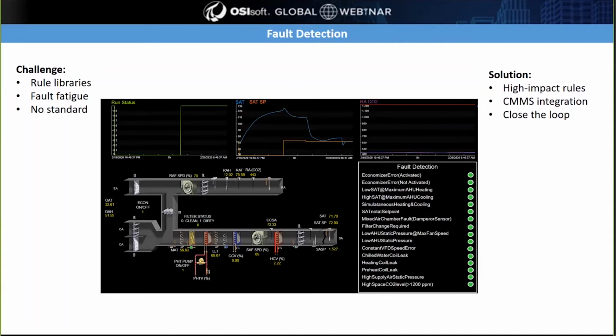But then there's a lot of rules that exist in libraries that aren't really valuable. So one example there would be any logic that checks for small temperature deviations from the temperature set points. So for example, if supply air temperature isn't within 2 degrees of set point, that's a rule that you can apply, but is it valuable? I don't really think so.